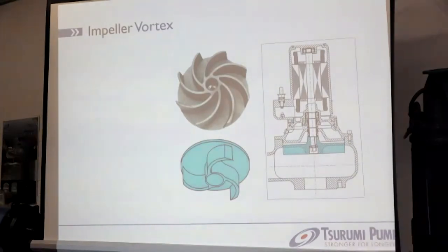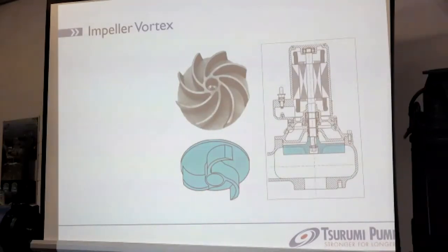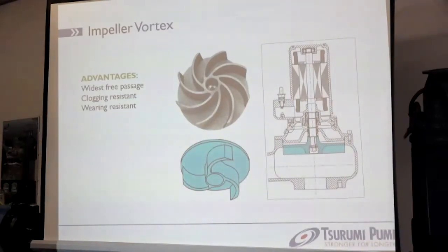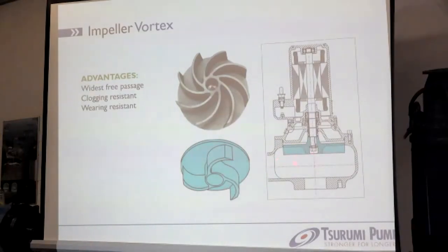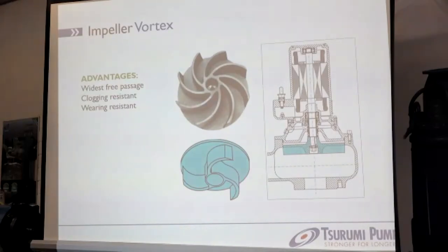The first impeller is the vortex impeller — the most simple technical design of impellers you can find. There are photos and a cut drawing of a pump with the vortex impeller. The advantages of the vortex impeller are the widest free passage among our possibilities, the highest clogging resistance due to that wide free passage, and the highest resistance against wearing. The pumping effect is not done by direct contact with the impeller; it is done by a vortex created by the rotation of the impeller — an indirect pumping effect.